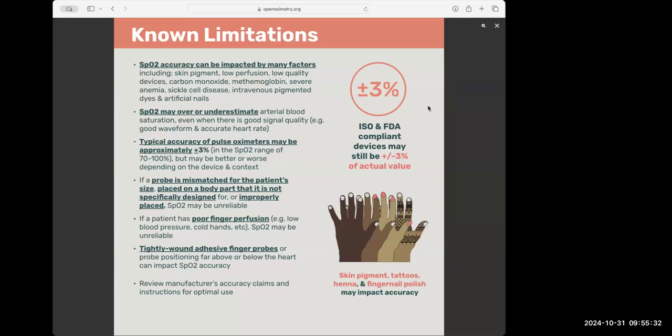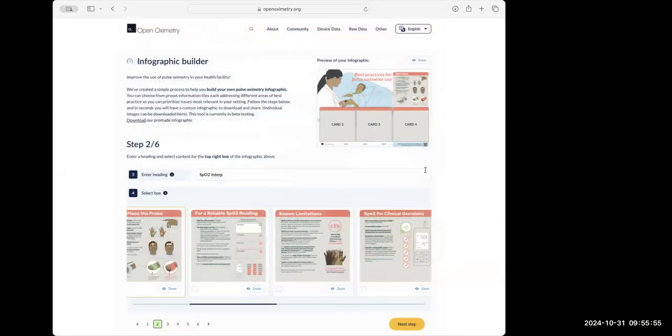Well, all devices have an uncertainty. And arguably that uncertainty is at least 2%. I was going to say the less money you pay, the wider that gets, but that's not true either. Some devices can have 3, 4, 5%. So all devices have uncertainty associated with them, which is why we get into this mess. Well, and sometimes you purposely pick a device for other aspects, knowing that you're only going to use it for trending, and you're accepting of that degraded accuracy because you know what it is.